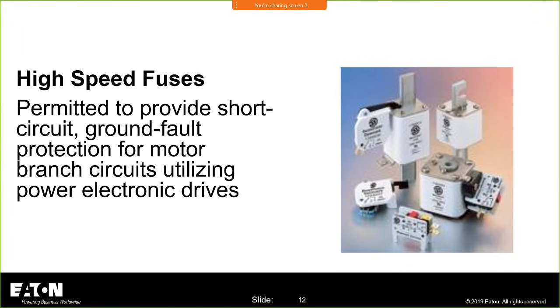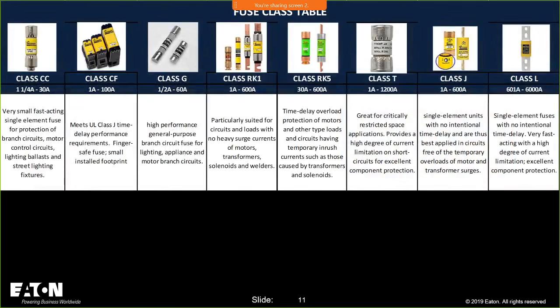Now, high-speed fuses. When I first started working at Bussmann, I moved over to the Bussmann group back, I'd say about 6 years ago or something like that. I've been with Eaton since 1995, however many years that's been. But I never knew what the heck a high-speed fuse was until I moved over there, because I never really got into the application of a high-speed fuse, because high-speed fuses are really used inside of equipment like variable frequency drives and things like that. And an interesting thing I learned about high-speed fuses, I'm used to the world of these fuses, where we do a load calculation. We figure out what the ampacity and what size conductor I need to use. And then once I know the conductor and the size of the conductor, then I go to 310.15(B) or 310.16, and then I find my overcurrent protective device size that will protect that conductor.